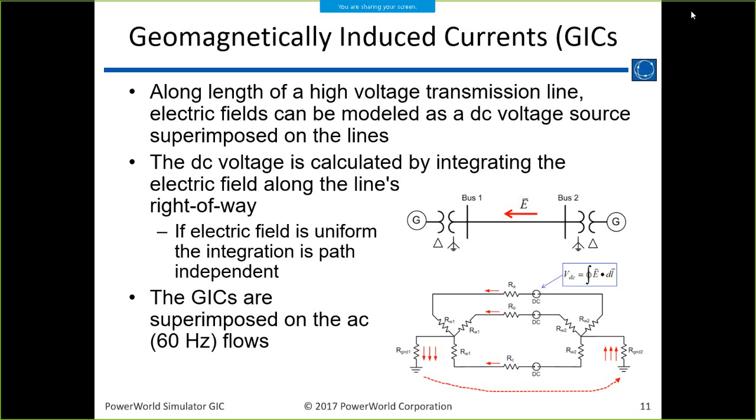So if I say, what's the temperature of that conductor? How do you know the temperature of your conductor? Or if you're doing a planning study, how would you know? What would you assume? Defined by the base case. Yeah, right. So it's whatever's in the base case. But in a power flow, the reactance and capacitance tend to dominate. Here, there is no reactance, so there's no susceptance, so it's just the resistance, and resistance is temperature dependent. So if you have a 50 degree C variation, you're going to have a 20 percent variation in your resistance values. That's just how copper and aluminum behave.